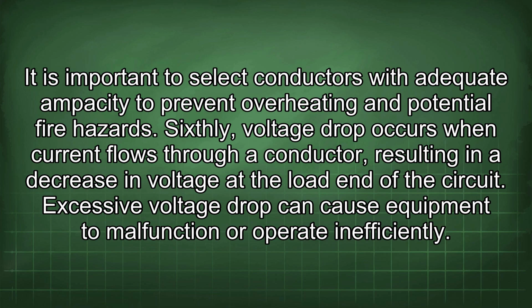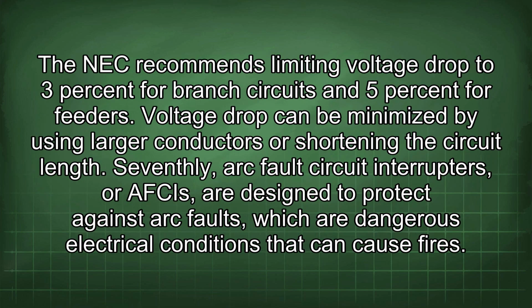Sixthly, voltage drop occurs when current flows through a conductor, resulting in a decrease in voltage at the load end of the circuit. Excessive voltage drop can cause equipment to malfunction or operate inefficiently. The NEC recommends limiting voltage drop to 3% for branch circuits and 5% for feeders. Voltage drop can be minimized by using larger conductors or shortening the circuit length.